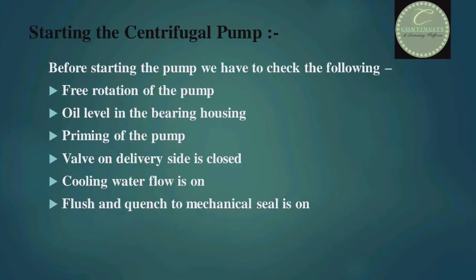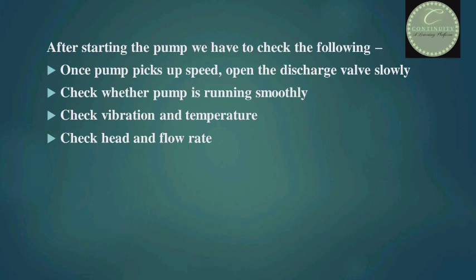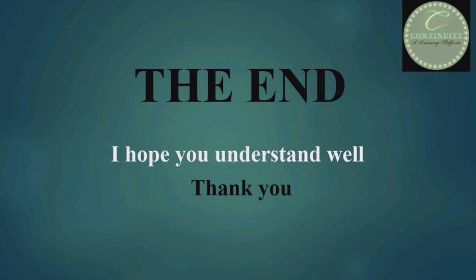Procedure for starting the centrifugal pump: Before starting, check the following — free rotation of the pump, oil level in the bearing housing, priming of the pump, valve on delivery side is closed, cooling water flow is on, and flush and quench to mechanical seal is on. After starting the pump: once the pump picks up speed, open the discharge valve slowly. Check whether the pump is running smoothly. Check vibration and temperature. Check head and flow rate. These are the complete steps involved in starting the centrifugal pump.